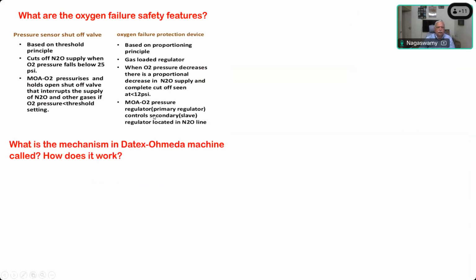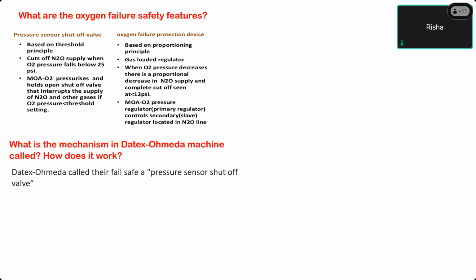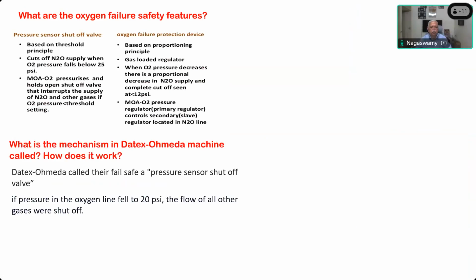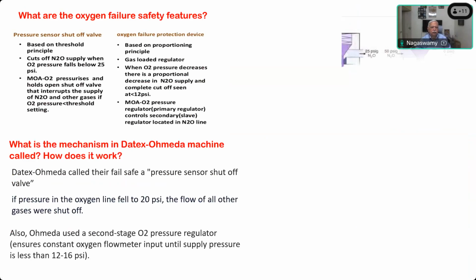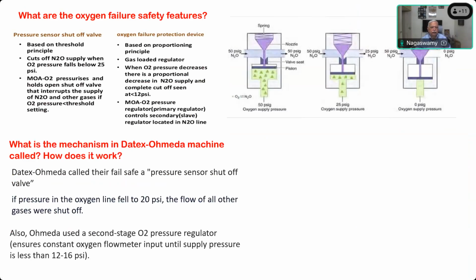What is the mechanism in the Datex-Ohmeda machine called for this oxygen failure and how does it work? This is a mechanical type with a bellows shut-off valve. If the oxygen line fell to 20 psi, the flow of all other gases was shut off. Also, Ohmeda used second stage oxygen pressure regulation. How the whole thing works.